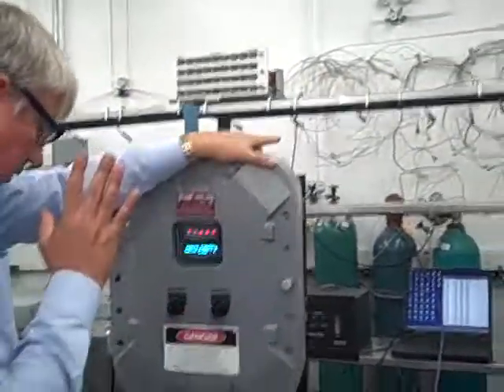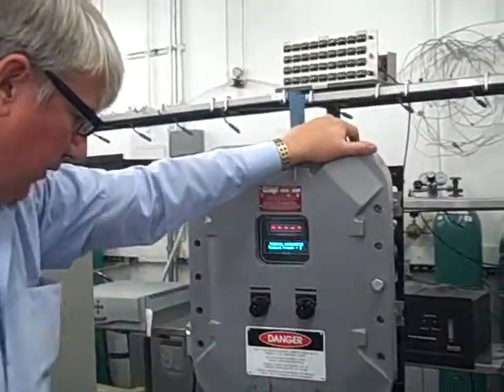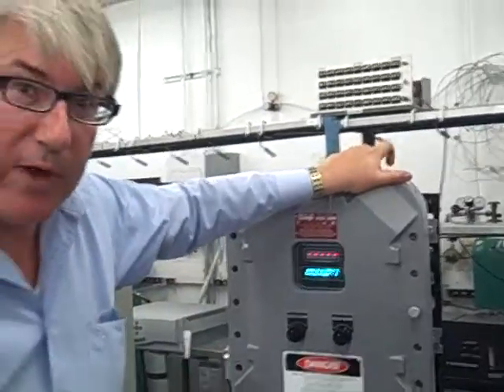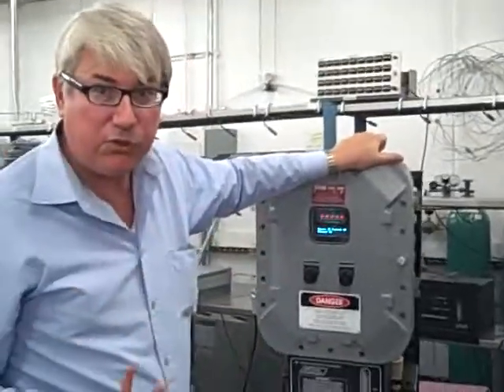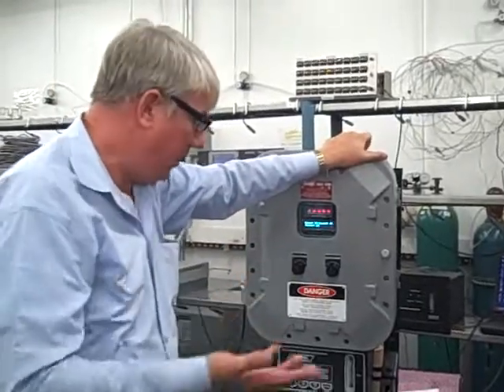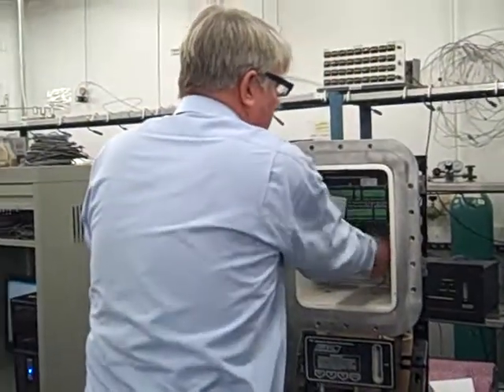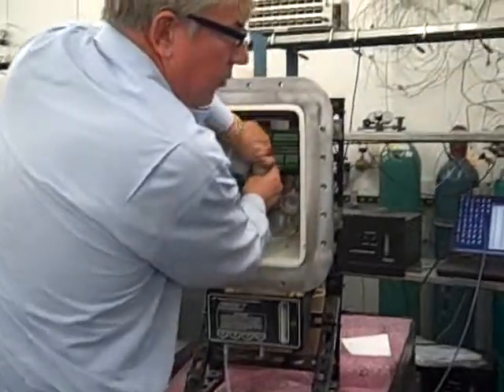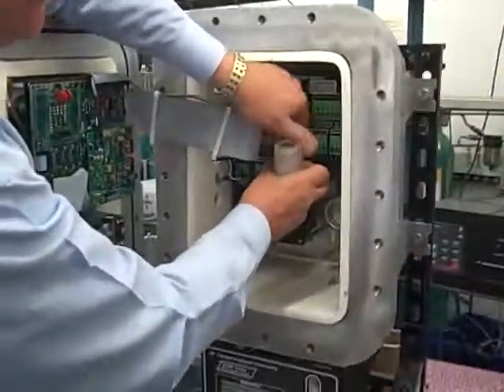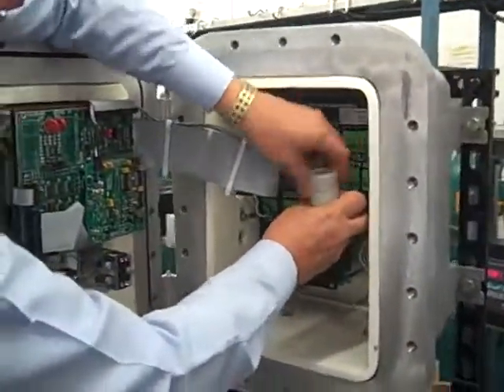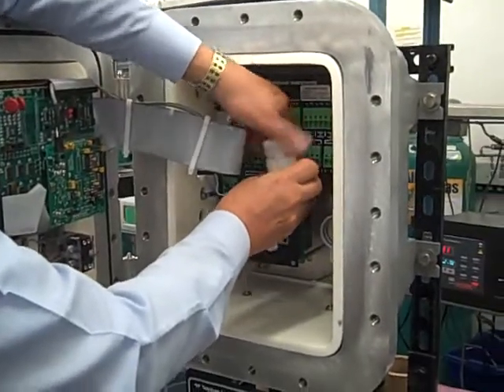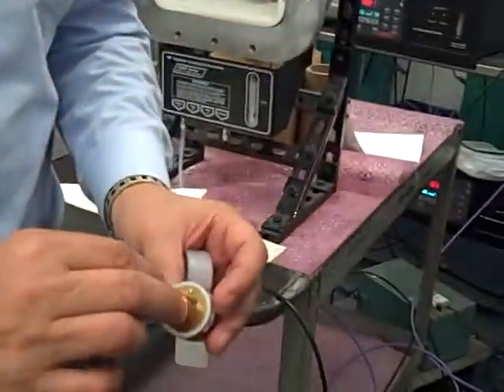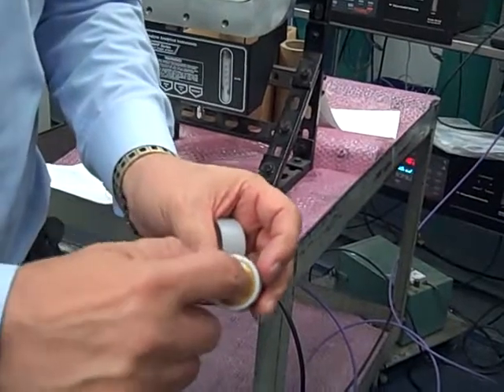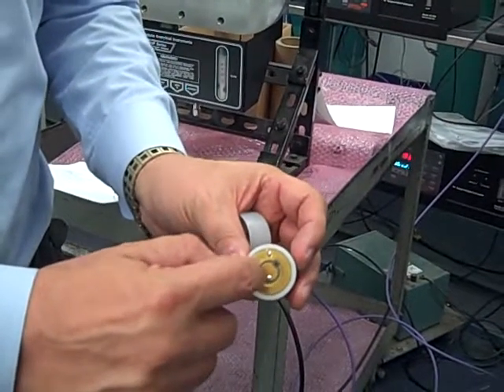We've covered the sensor installation. We've covered the basic theory of operation of the sensor. What it does is it produces a current that's linear to the amount of oxygen. In fact, one thing I can show you, if you have some question about whether your sensor is good or not, there's a very easy test to do. Very simple. Any electronic technician can do it. Remove the sensor, expose it to air, put it down on a table, and then measure with a multimeter in ampere mode the current from the contact surface in the middle to the contact ring on the outside.